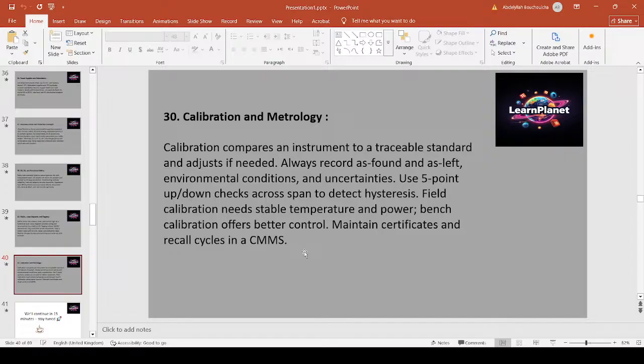Calibration and metrology. Calibration compares an instrument to a traceable standard and adjusts if needed. Always record as-found and as-left values, environmental conditions, and uncertainties. Use 5-point up-down checks across span to detect hysteresis. Field calibration needs stable temperature and power. Bench calibration offers better control. Maintain certificates and recall cycles in CMMS.